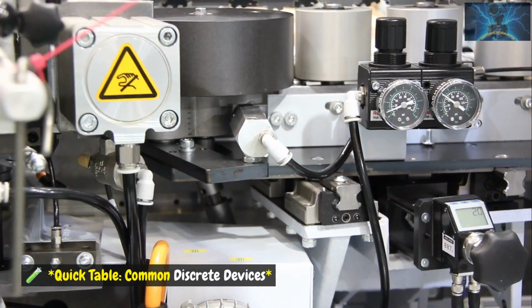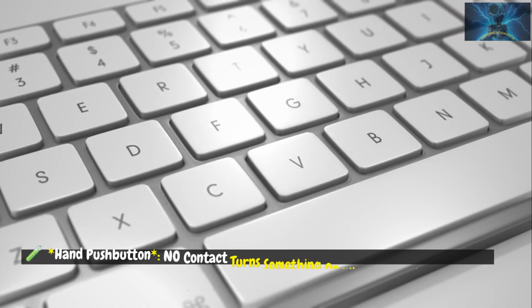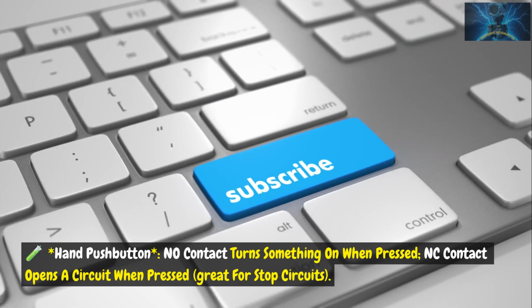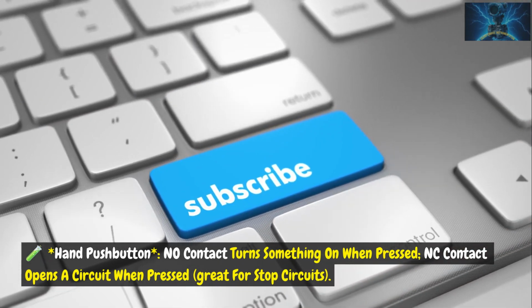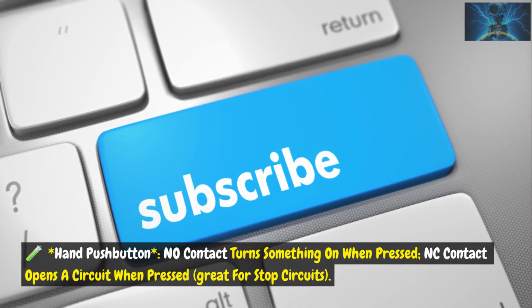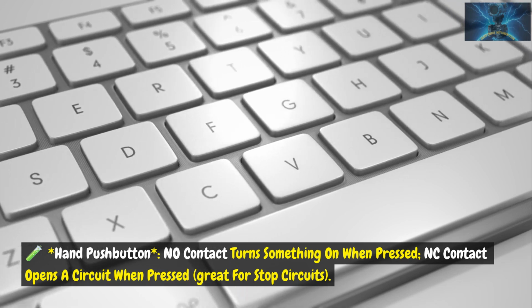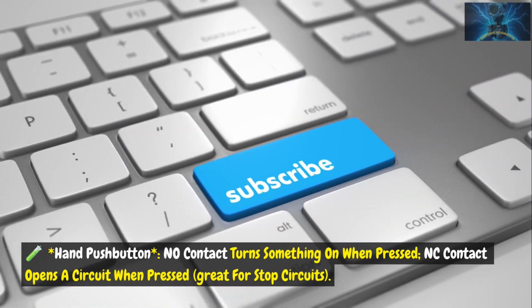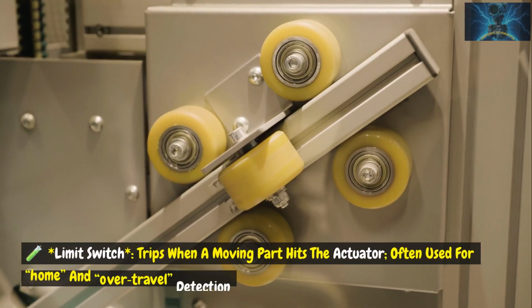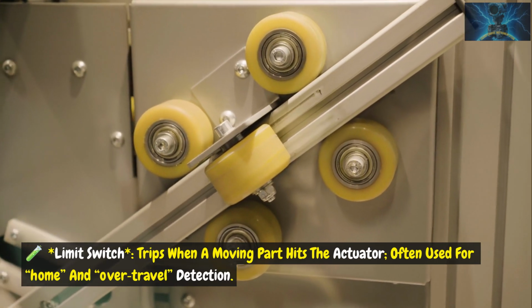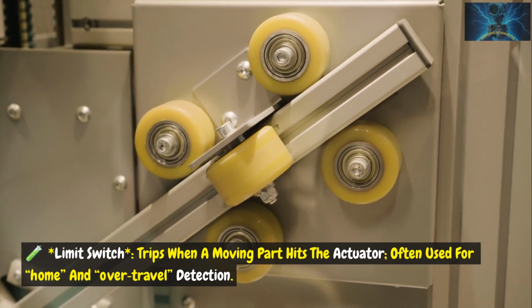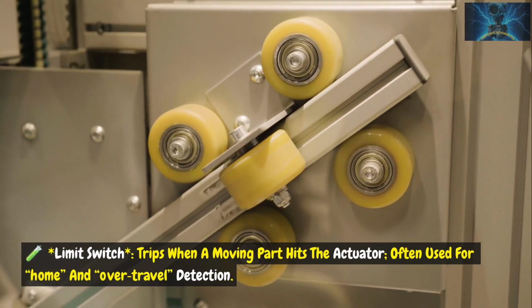Quick table: common discrete devices. Hand push button: NO contact turns something on when pressed. NC contact opens a circuit when pressed, great for stop circuits. Limit switch: trips when a moving part hits the actuator, often used for home and over-travel detection.